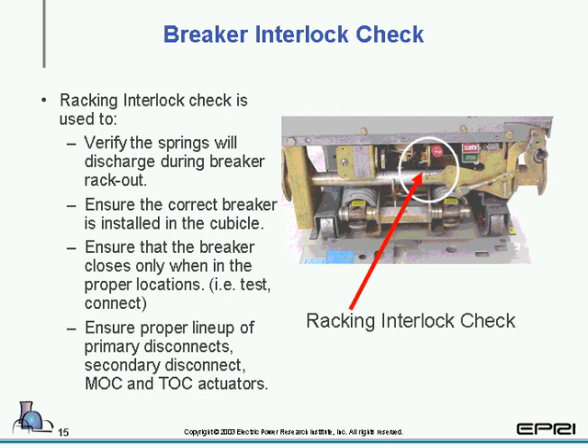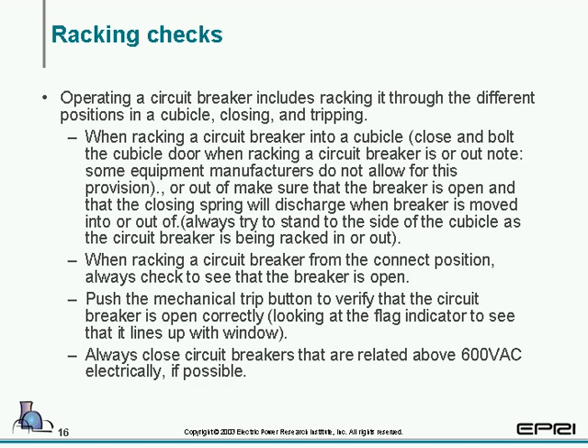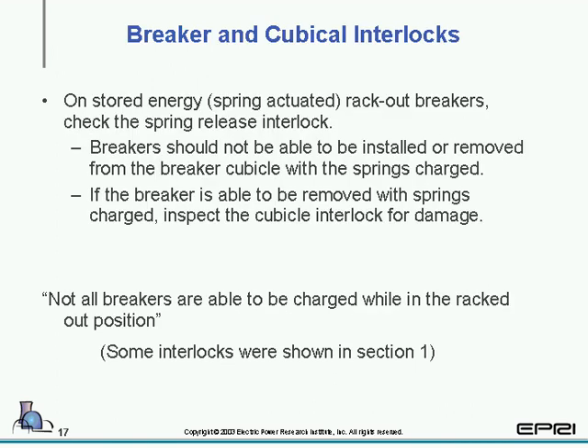As we talked about in section 1, we're going to take a look at interlocks and racking interlocks. It's very important that the springs will discharge during breaker rack out for the very first item. And we have a list of others. On this particular slide, we're going to be taking a look at the operating circuit breaker, including racking through the different positions. And we spoke about this in session 1. And we pretty much gave another outline as breaker cubicle interlocks. And again, not all breakers are available to be charged while in the racked out position. And as spoke about in session 1.